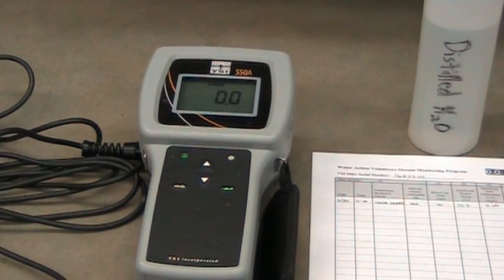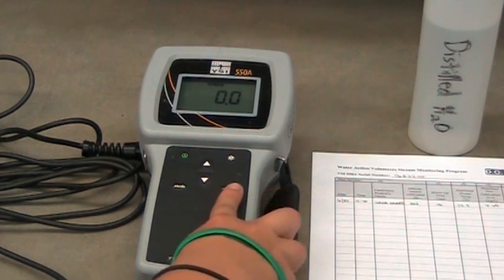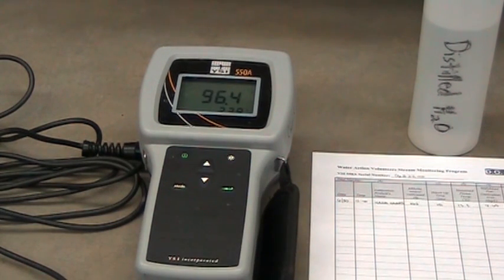The salinity of the sample will appear on screen. Press enter again to accept zero salinity as we are testing fresh water. The calibrated percent saturation should now appear on the screen and the CAL in the lower left-hand corner should have disappeared.